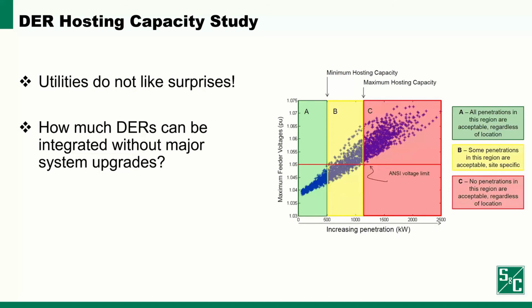This study is called DER hosting capacity. What it basically does is that when a utility receives a request for DER installation and needs to know how much DER can be hosted by each given feeder, they tend to perform this analysis. So at that point, they know the capacity for each distribution feeder before the system would really be technically challenged. The objective of the study, as I said, is to determine the maximum amount of DER that each distribution feeder can host. There are technical thresholds, mostly voltage limits and also the thermal capacity of the feeders, that are usually closely monitored to see at which point those will be exceeded.